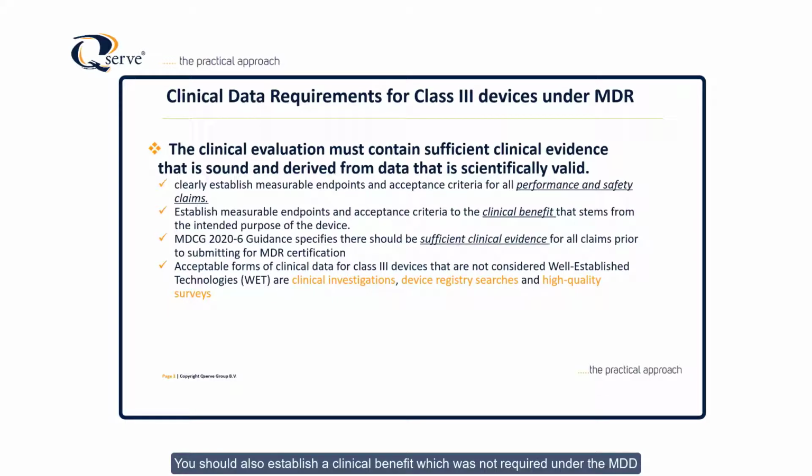You should also establish a clinical benefit, which was not required under the MDD, but is now required under the MDR. And again, you want a measurable endpoint and acceptance criteria for the clinical benefit, the positive impact to the patient that stems from the intended purpose of the device.